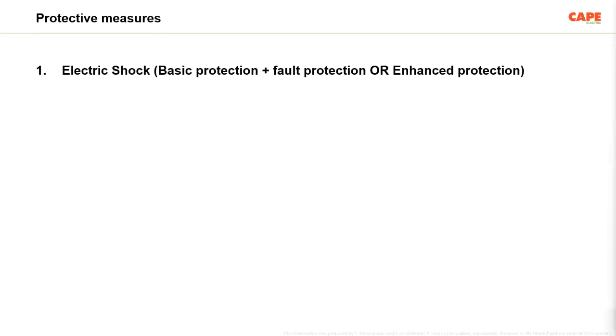These safety measures, disconnection, double insulation, electrical separation of one equipment, and extra low voltage, are the ones which can be implemented in a general location, that means where common people are available. Whereas in an industrial environment, sometimes you need much different safety measures, for environments where you have people who are instructed or skilled. In that area, the safety measures which can be implemented are sometimes called a non-conducting location, earth-free local equipotential bonding, and electrical separation of multiple electrical devices from one power supply. So like that, shock protection can be achieved by various protective measures.